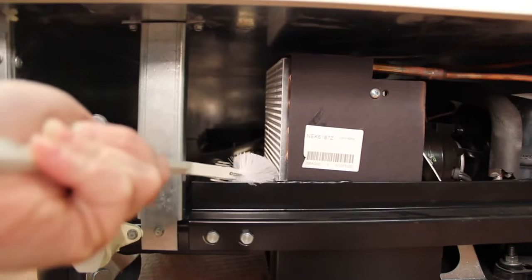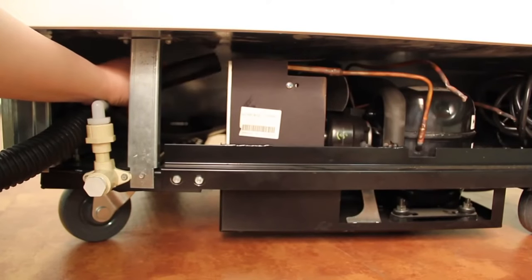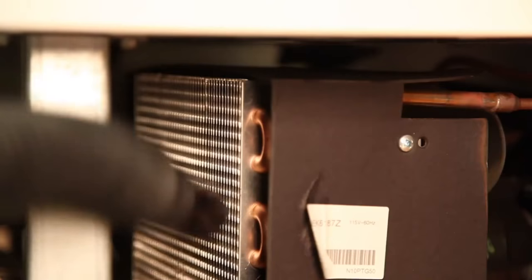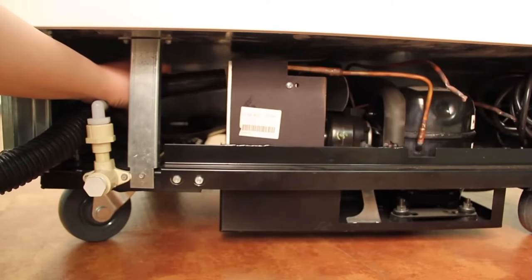After brushing the condenser coil, vacuum the dirt from the coil. Again, moving the vacuum up and down the coil and never side to side as this could bend the fins on the coil.